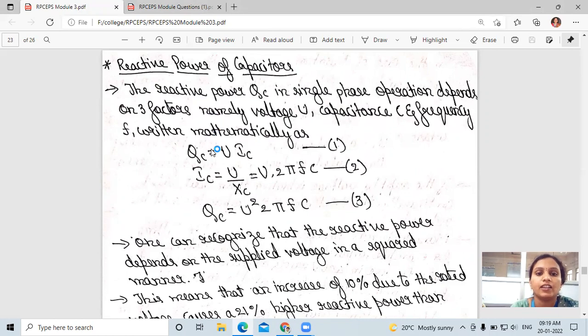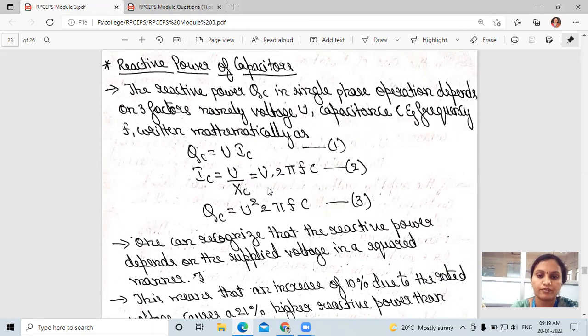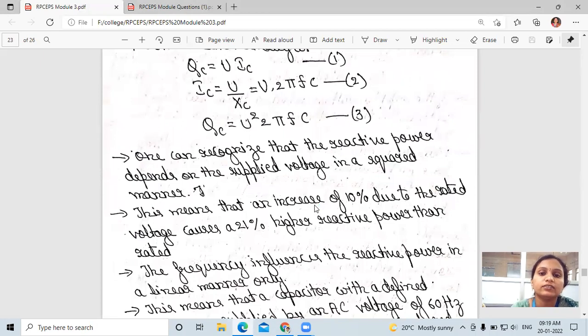We can write this in equation form: Qc is equal to U into Ic. Ic can be written as U divided by Xc, where U is voltage. We can also write Xc equal to 1 divided by 2πFC, so Ic equals U into 2πFC, and therefore Qc equals U² into 2πFC.